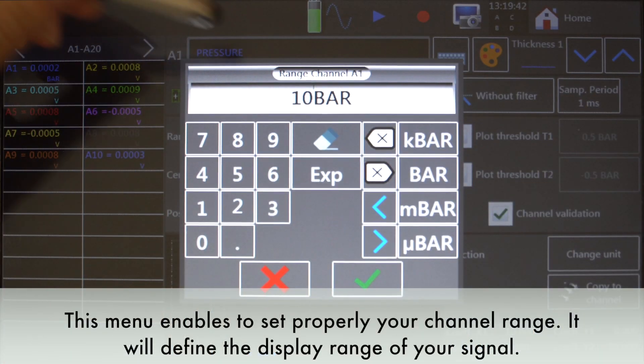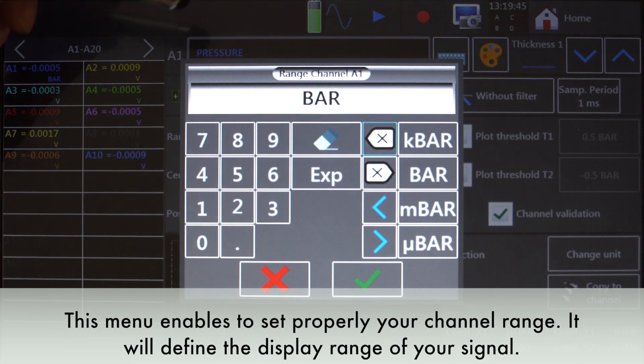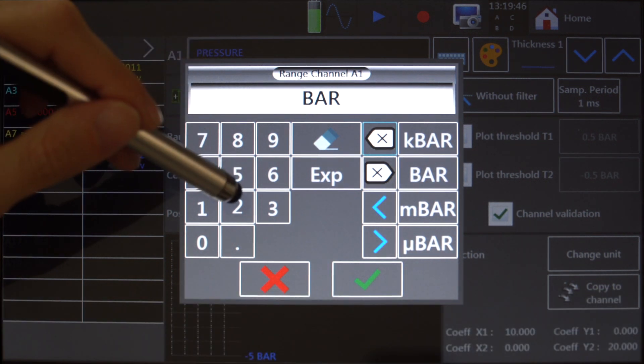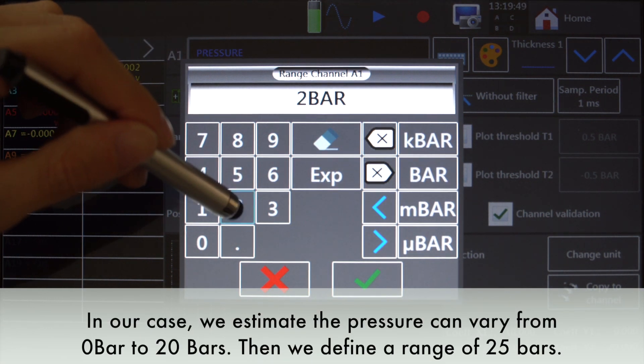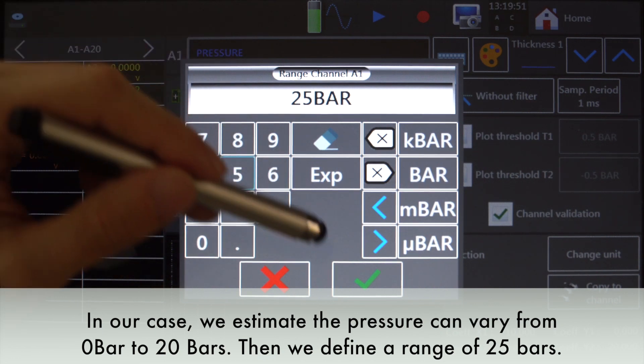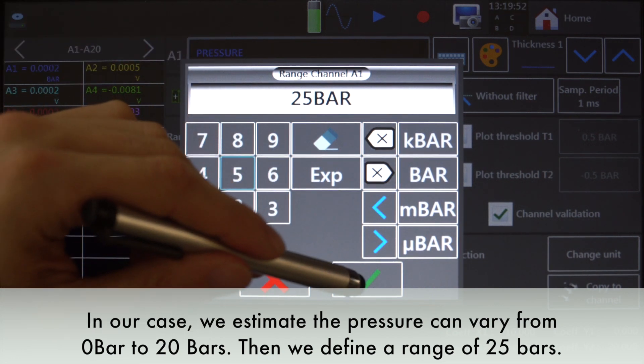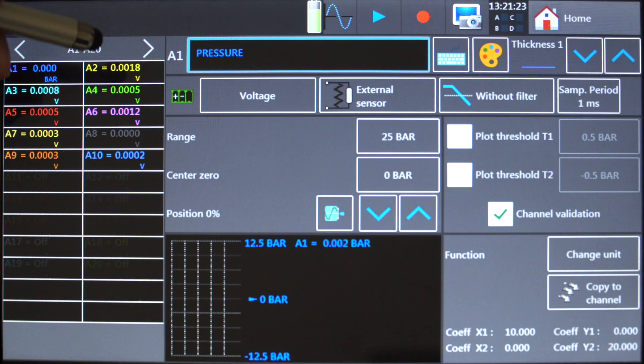This menu enables to set properly your channel range. It will define the display range of your signal. In our case, we estimate the pressure can vary from 0 bar to 20 bars. Then, we define a range of 25 bars.